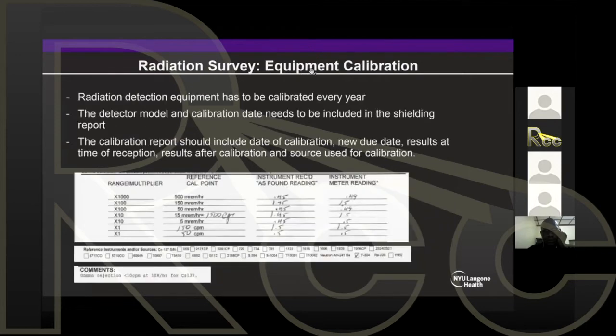And regarding calibration, you need to ensure that all your survey meters are calibrated, right? Here we calibrate them every year. The detector model and calibration date need to be included in the shielding report. And also your calibration report for the instrument should include the date of calibration, the new due date, results at time of reception, results after calibration, and the source used for calibration. So that's very good to make sure that there's nothing wrong with your detector.